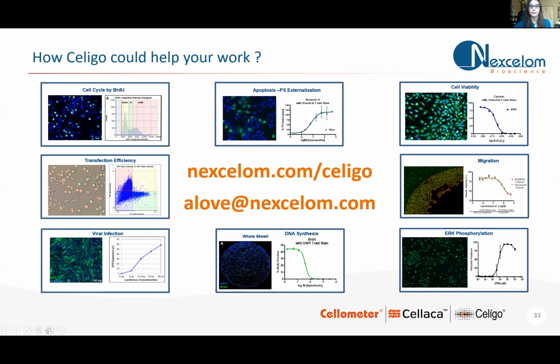Wonderful. And then Andy Morshauser asked, are single color controls necessary for compensation? That's a great question. Now, typically no, and that's because we're using LED-based light sources that have paired excitation emission, and they're only illuminating independently.